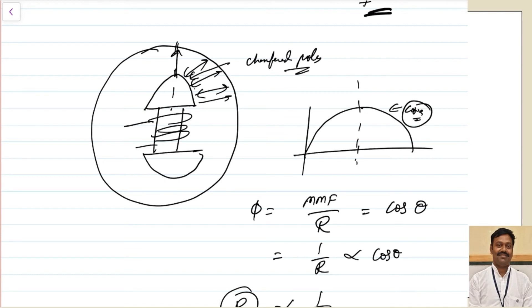Another way to reduce space harmonics is to make the winding such that the gap between two adjacent slots is as small as possible. When the gap between adjacent slots is minimized, the variation of reluctance decreases and the flux becomes more uniform. In other words, we should distribute the slots such that the maximum possible number of slots are used — this automatically makes your flux wave nearly sinusoidal. This is the way you can eliminate your space harmonics.